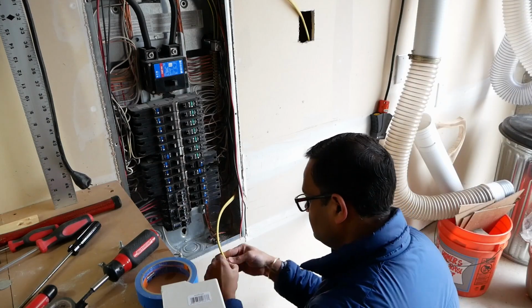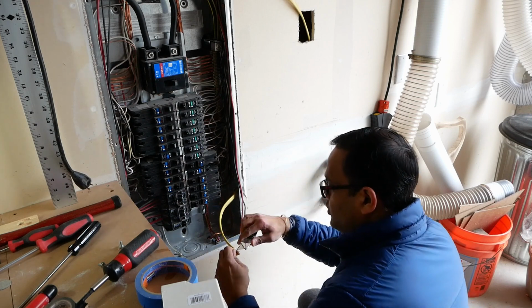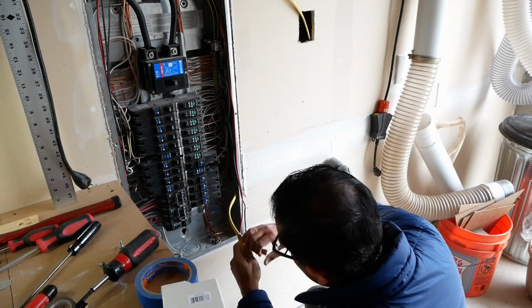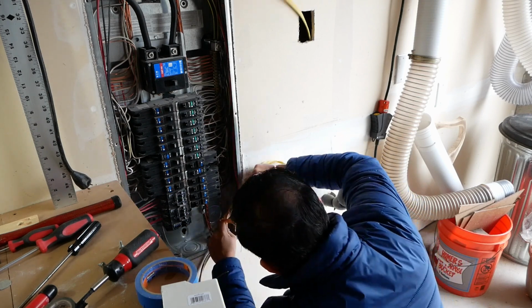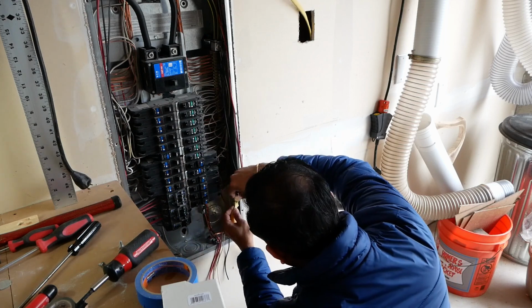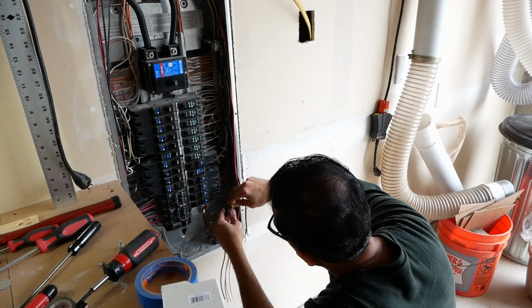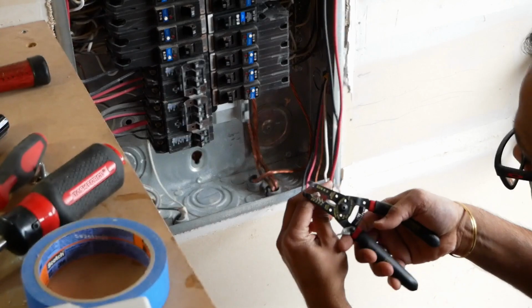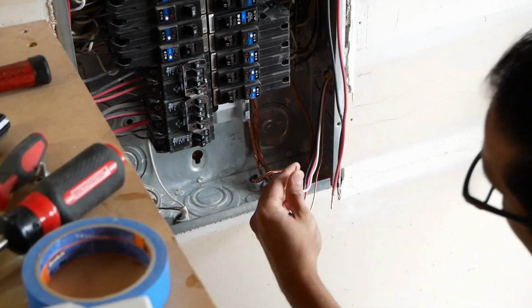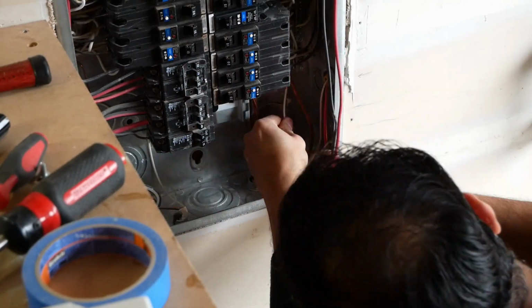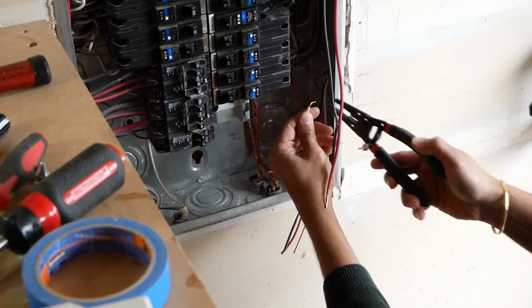The next step is to make the connections. For 240 volt breakers, there are 2 hot wires. In this case, we have a red and a black wire. In addition to the hot wire, we also have a neutral and a ground. Both of these go to the neutral bar, which is there on the panel. In the case of the main panel, both the neutral and the ground are connected to the same bar.